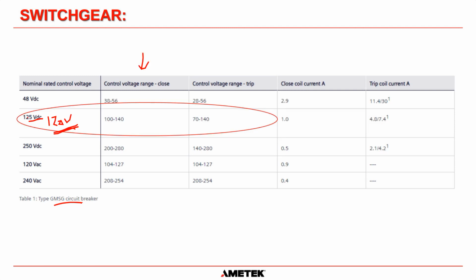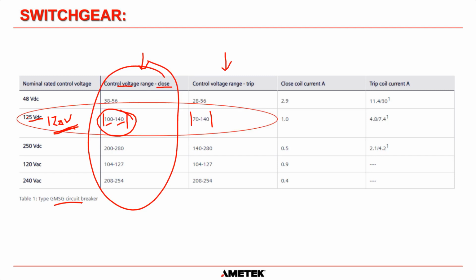But if you look in this column here, it's saying the voltage range to allow that breaker to close is 100 to 140 volts DC. And if you go into this next column here, for this particular type of breaker, to trip that breaker, the voltage must be between 70 and 140 volts DC. So this one here is what we have to conform to. Therefore, the DC from our battery and charging system cannot go above 140 volts and should not go below 100 volts to allow the closing of this breaker.